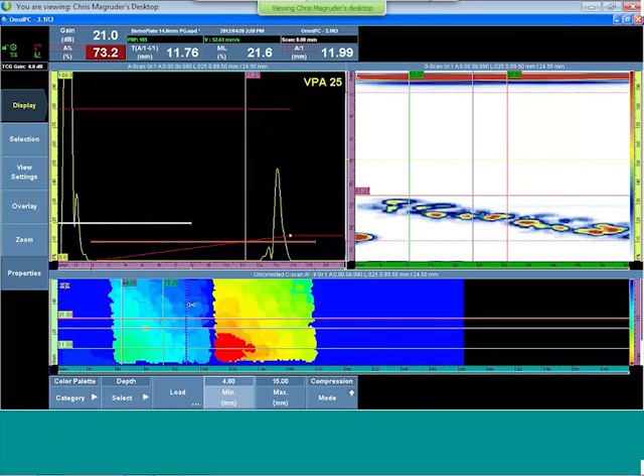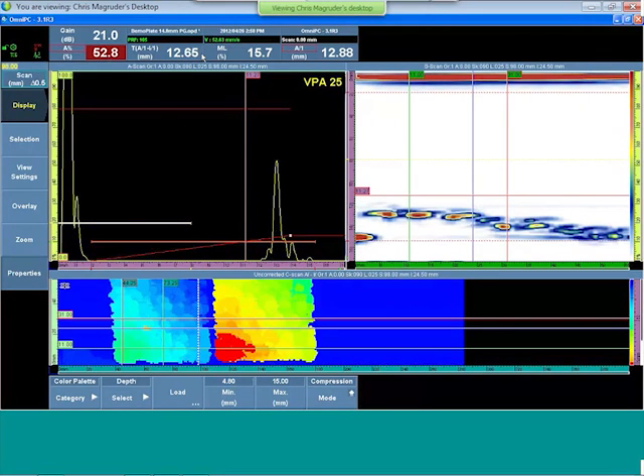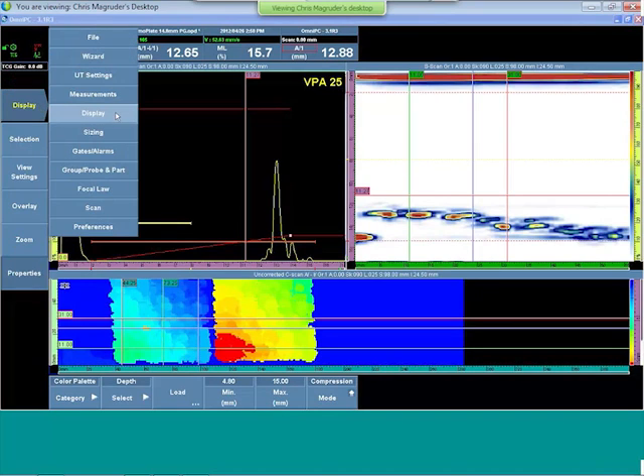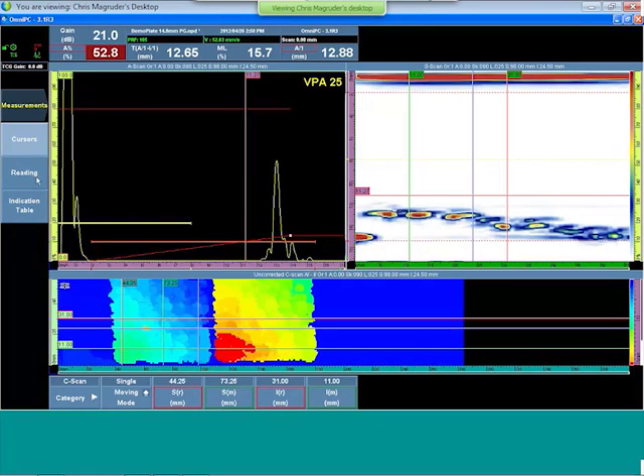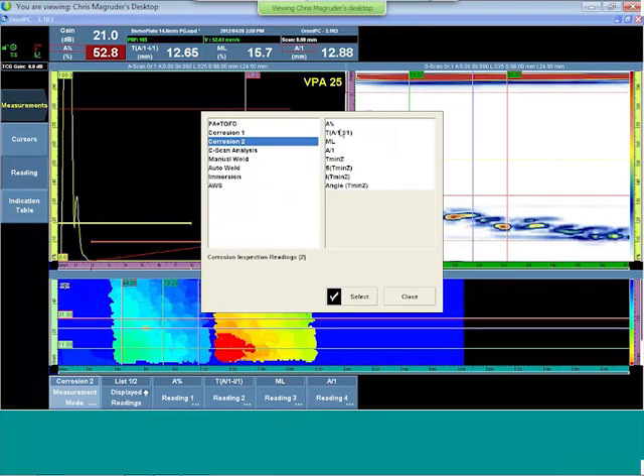Now, our readings here, in the OmniScan, you have 2 lists of 4 readings each that will appear on the report and at the data file. Since we're saving the full A scan, those can be changed at any time. If you use one of the default files, in those are already pre-configured lists of useful readings typically used with corrosion.